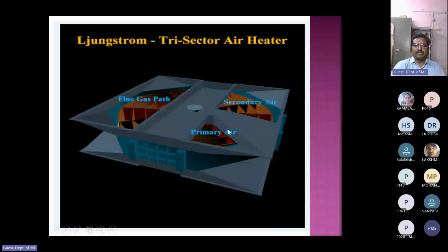When it is rotating, in this condition, when flue gases flow through this basket, the basket receives the heat energy from the hot flue gases and stores it inside the basket. When the basket rotates and comes here, cold air flows over the basket. So this cold air receives the energy from the basket and its temperature rises. The primary air also flows through the basket. Okay, this is the cross section of the regenerative air preheater.